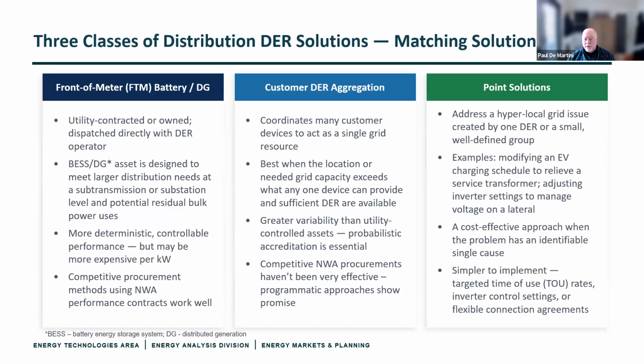You're dealing with the issue right at the point where it's created. The other thing developing over the last two years are flexible connection agreements, both flexible interconnection and flexible service connections. Flexible service connections have largely been used for fleet charging and public charging facilities, where they agree not to exceed a certain consumption limit, mitigating the potential overload or constraint and the cost to upgrade that might otherwise be required.